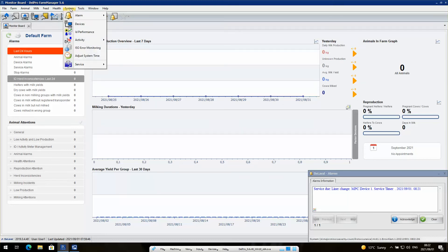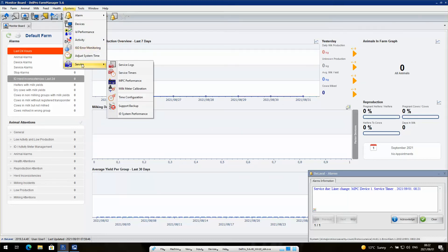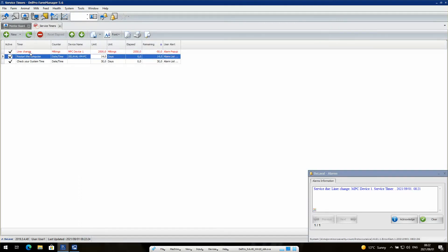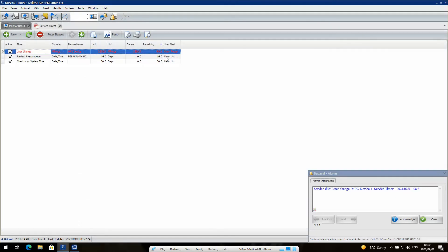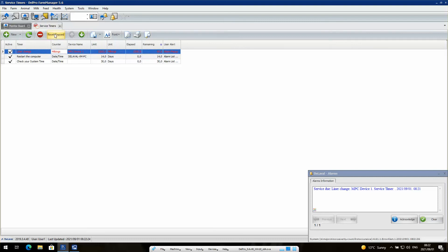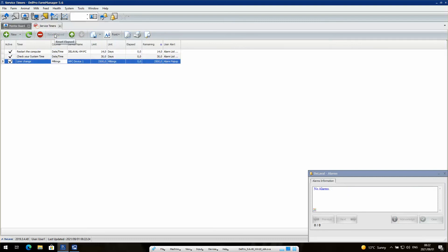I go to System, I go to Service, I go to Service Timers. I then select the service timer that's been brought to my attention, select it, and click Reset Elapsed — and the elapsed value goes down to zero.